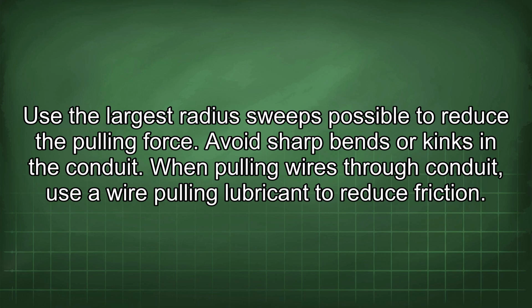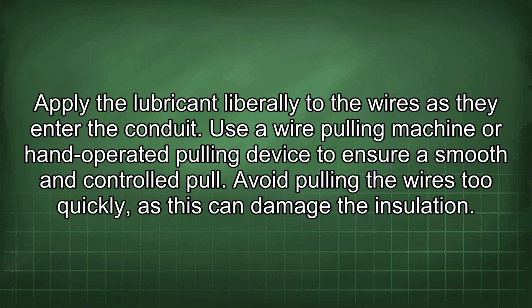When pulling wires through conduit, use a wire pulling lubricant to reduce friction. Apply the lubricant liberally to the wires as they enter the conduit. Use a wire pulling machine or hand-operated pulling device to ensure a smooth and controlled pull. Avoid pulling the wires too quickly, as this can damage the insulation.